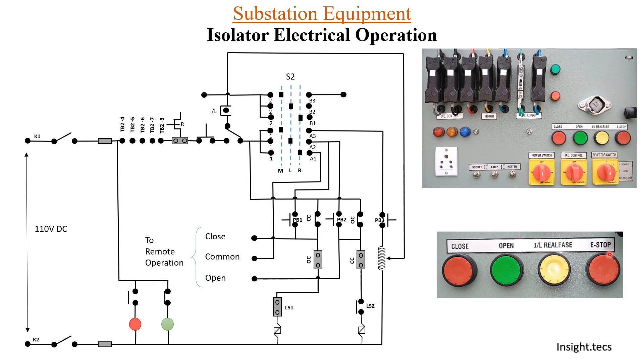After the overload relay NC contact, there is the E-stop — emergency stop push button. If you are carrying out any operation of the isolator and there is an emergency and you need to suddenly stop the operation, you can use this E-stop push button. Once this push button is operated, the DC will be disconnected at this point and DC will not go forward.